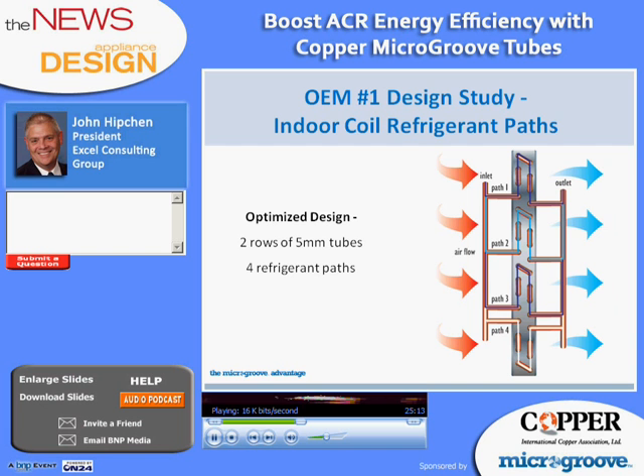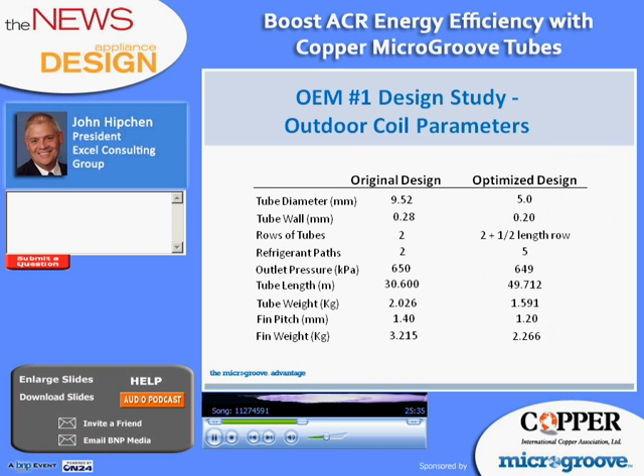Here is a circuit diagram for the indoor coil with the optimized design showing the 4 refrigerant paths. This is much less restrictive path for the refrigerant, and it will result in a lower, more acceptable refrigerant pressure drop across this indoor coil. So now let's look at the outdoor coil. We're going to look at this just as we did with the indoor evaporating unit, and we'll compare the original design of the outdoor condensing coil with the optimized design.